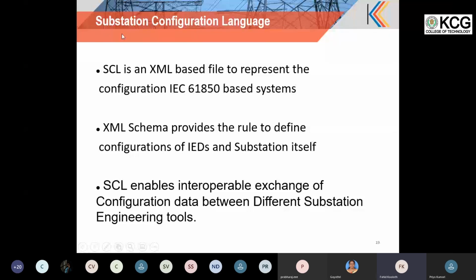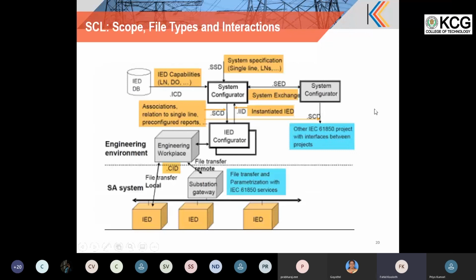So SCL enables the interchange of configuration between multiple engineering and different tools. I have a snapshot of the tools available for this exchange. Let's go with a top to bottom approach, taking a configuration scenario from top to bottom. First thing we need to do is a specification for a substation. That is, connect this breaker, this is a voltage level, then this breaker is coming, this transformer is coming, and this connection needs to be completely defined. We call it a single line diagram. That is nothing but a substation specification.